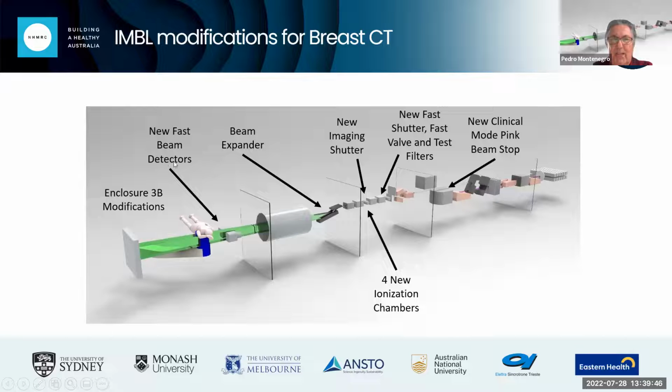Basically, what happens in the case of the iPass, if for something that we cannot really figure out how it could happen, but that's the way you design a safety system. If when iPass thinks or knows that all the safety shutters are closed, these detectors detect any photons at all in the imaging bunker, they give, through the iPass, a direct order to the storage ring to kill the radio frequency cavities.